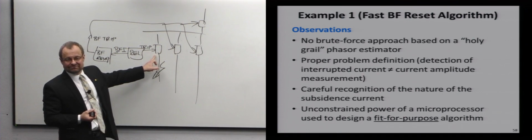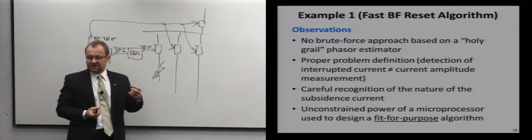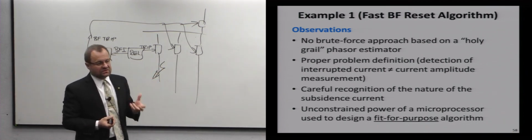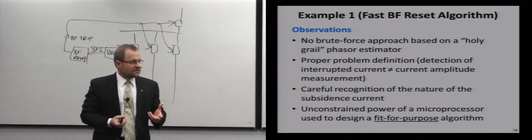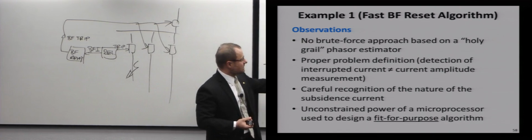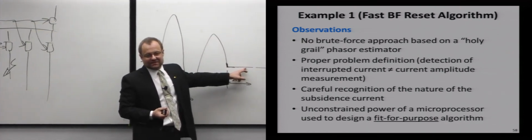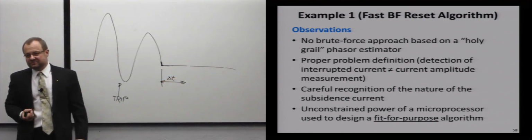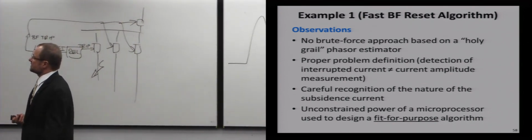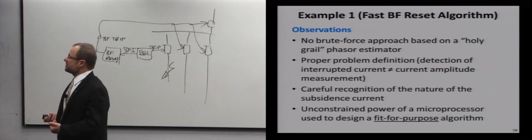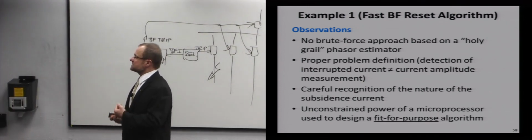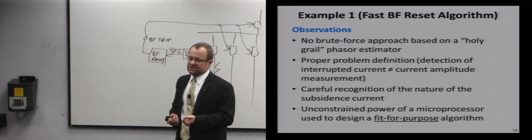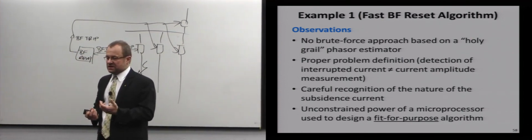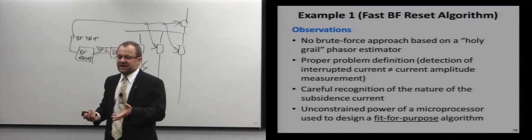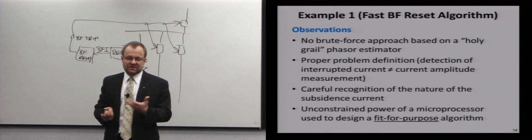The question wasn't about what's the magnitude of the current. The way to detect it is through measuring the current, but it's not about the magnitude of the current. I couldn't care less how accurately I measured at zero. It's kind of irrelevant because I am expecting to measure the zero, right? So it's not a brute force holy grail approach. The problem is defined properly, meaning that detection of the interrupted current is different than measuring the current magnitude. Only a brute force approach would give me the magnitude estimator that is very fast. So I could just check it against the threshold and be done with it, right?